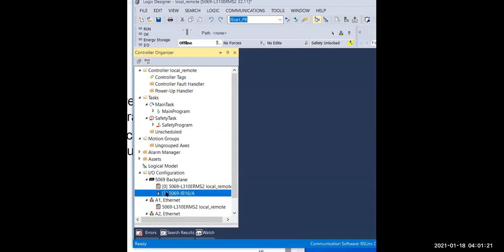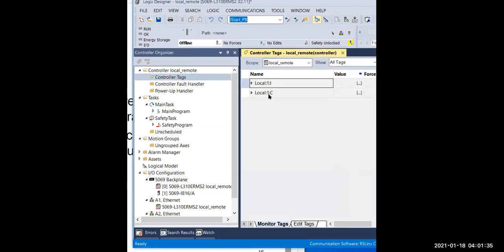You can see here — we have a module created. I represents input, binary digital, 16 channels. This is the module we created. Then we can go to the controller tag level — you can see right here you have Local:1.I (input) and also Local:1.C. Remember, C represents configuration.